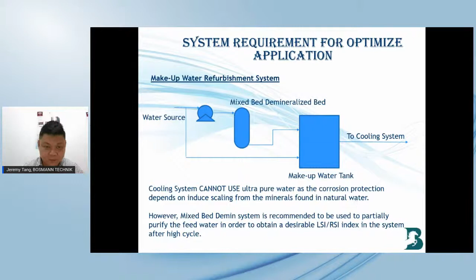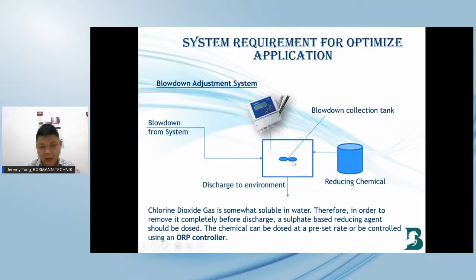Okay, the second part is the blowdown adjustment system. Before blowdown, we have to discharge into a tank, or if the piping is long enough and the so-called retention time is enough, we have to dose in some reducing chemical to neutralize the chlorine dioxide gas, which is soluble in water, so it can be completely discharged and meet the DOE requirement.